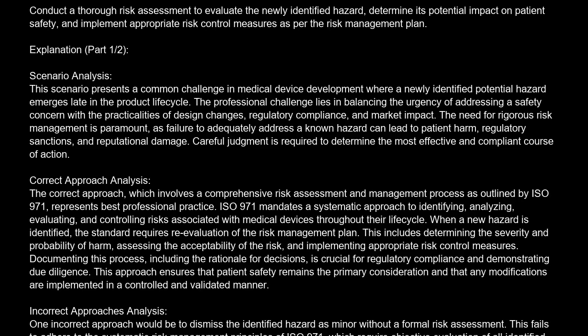The correct answer is B. Conduct a thorough risk assessment to evaluate the newly identified hazard, determine its potential impact on patient safety, and implement appropriate risk control measures as per the risk management plan. Explanation. Scenario analysis. This scenario presents a common challenge in medical device development where a newly identified potential hazard emerges late in the product lifecycle.